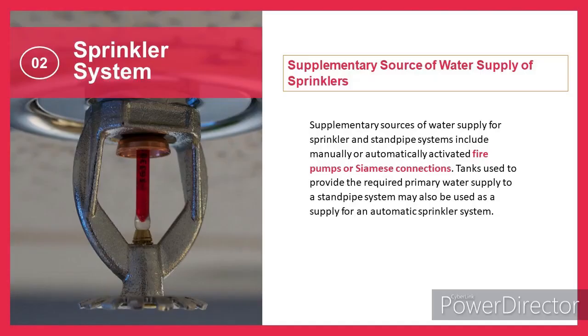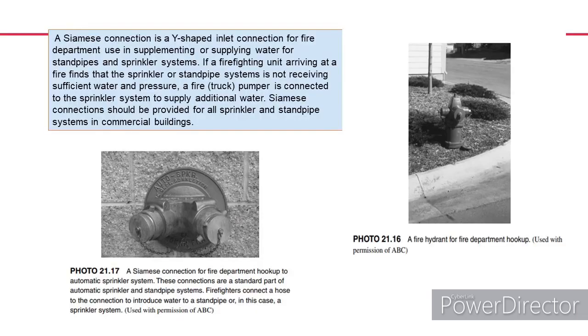There is also a supplementary source of water supply of sprinklers. This includes manually or automatically activated fire pumps or Siamese connections. Tanks used to provide the required primary water supply to a standpipe system may also be used as a supply for an automatic sprinkler system. A Siamese connection is a Y-shaped inlet connection for fire department use in supplementing or supplying water for standpipes and sprinkler systems. If a firefighting unit arriving at a fire finds that the sprinkler or standpipe system is not receiving sufficient water and pressure, a fire truck pumper is connected to the sprinkler system to supply additional water. Siamese connections should be provided for all sprinkler and standpipe systems in commercial buildings.